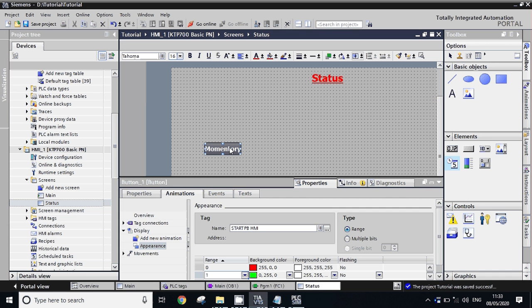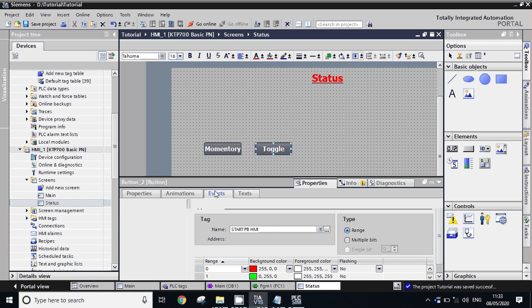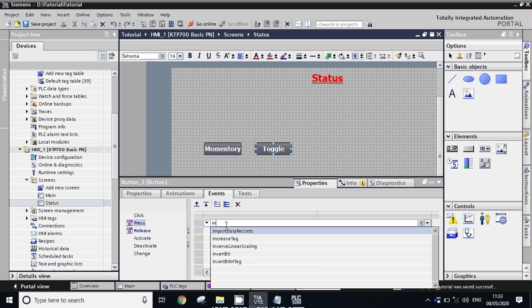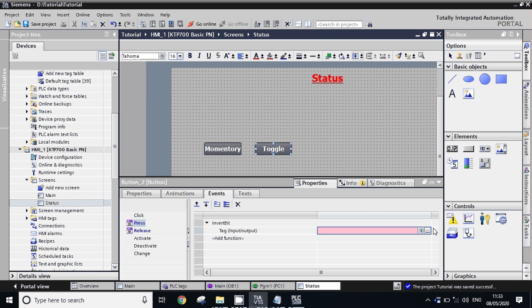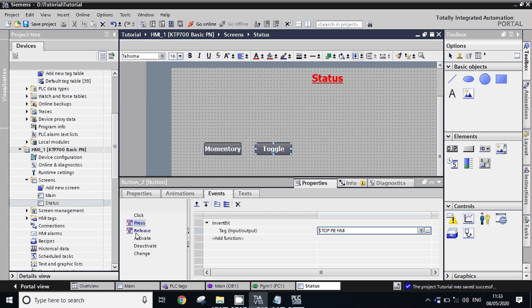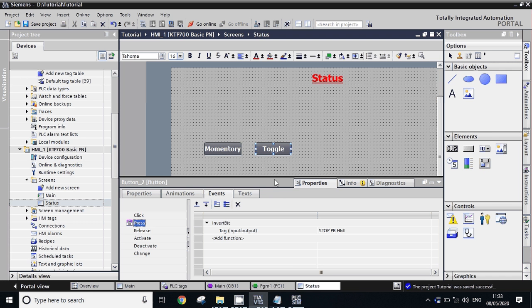We will copy this button and paste it to make it a toggle or maintain button. Go to Properties and change the event to 'Invert Bit'. Take another tag here — M0.2. Now delete the release event — no need for release here. So how it will work: whenever we press this button the tag inverts, meaning if it is 0 it will become 1, and if it is 1 it will become 0. This is the toggle button.